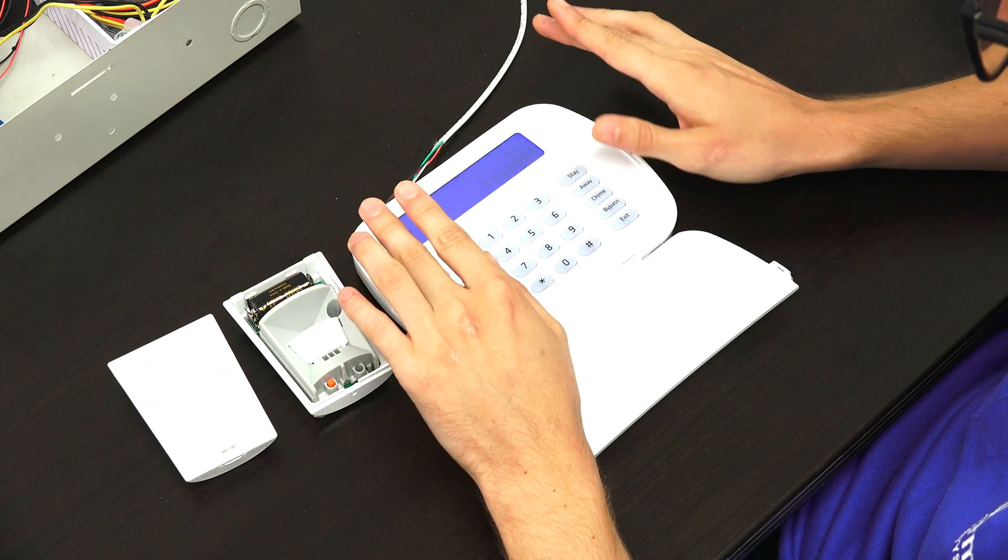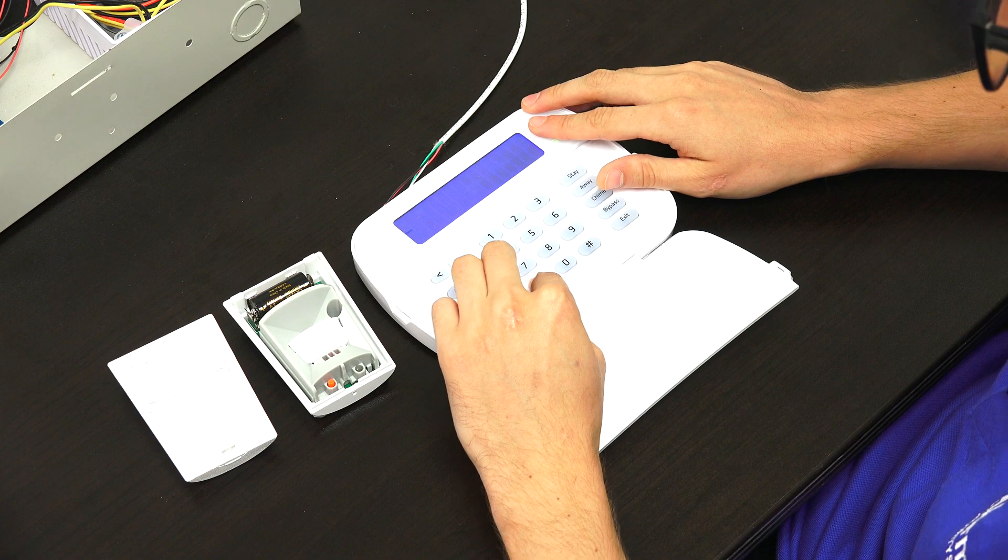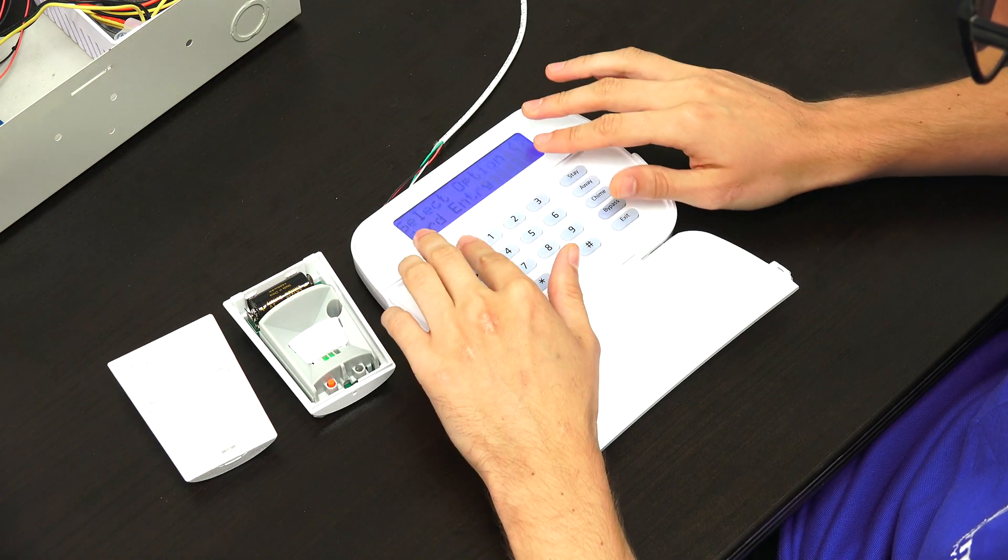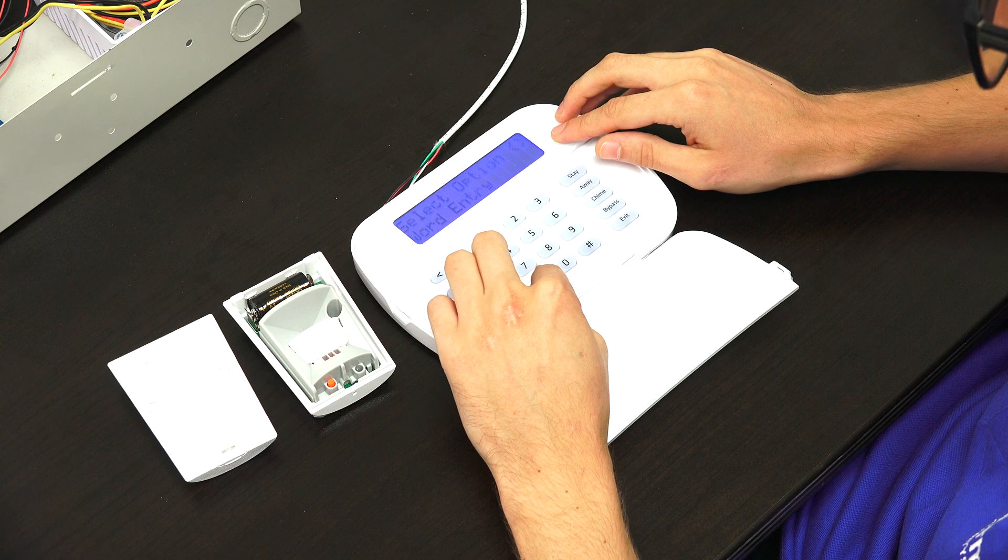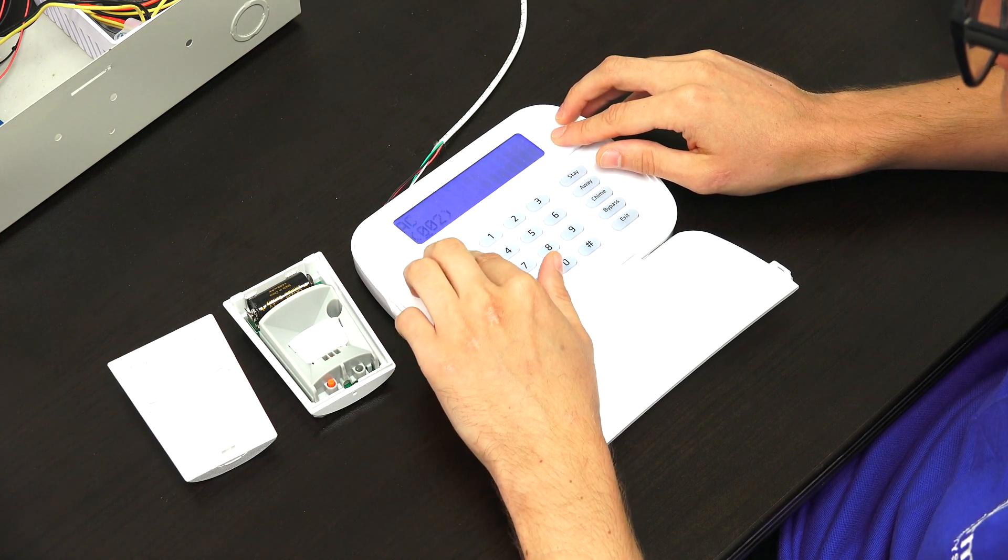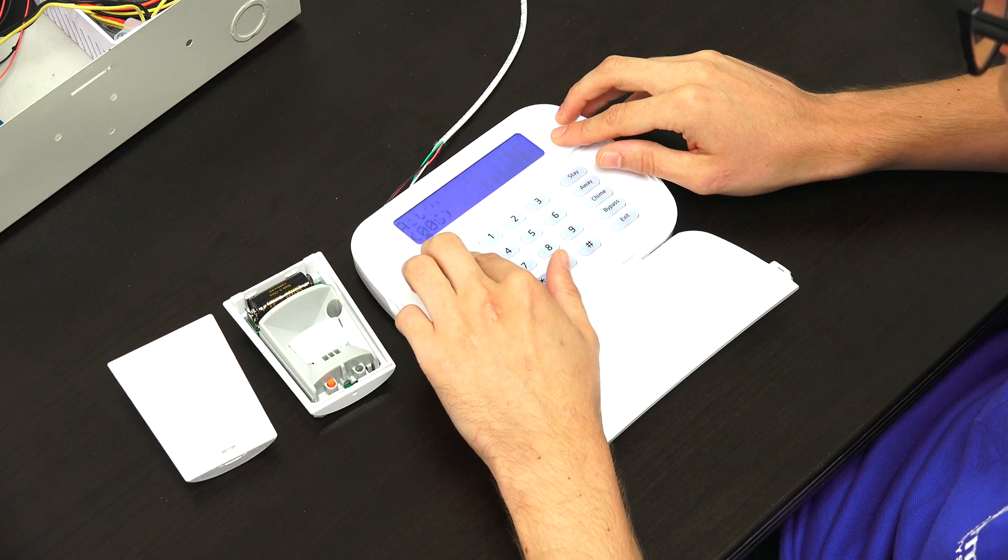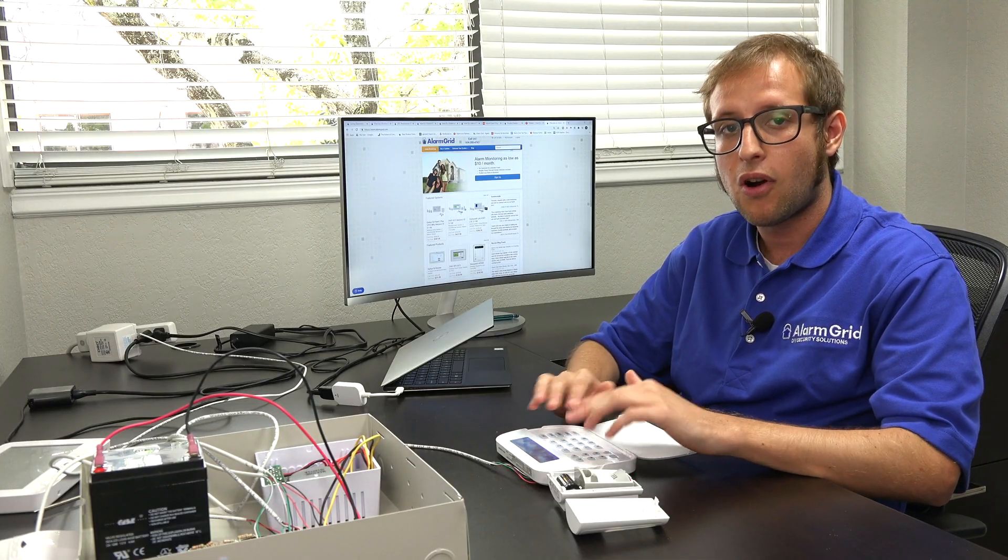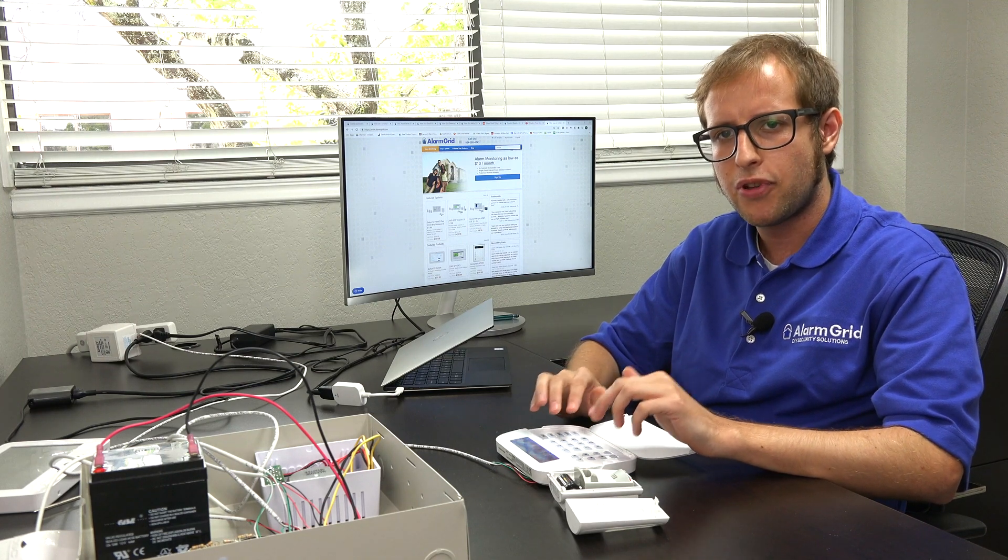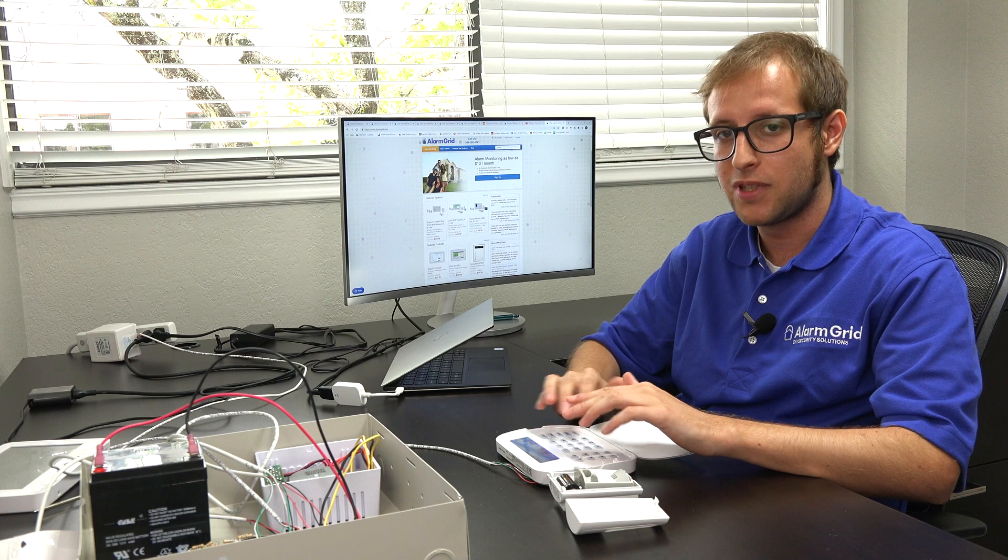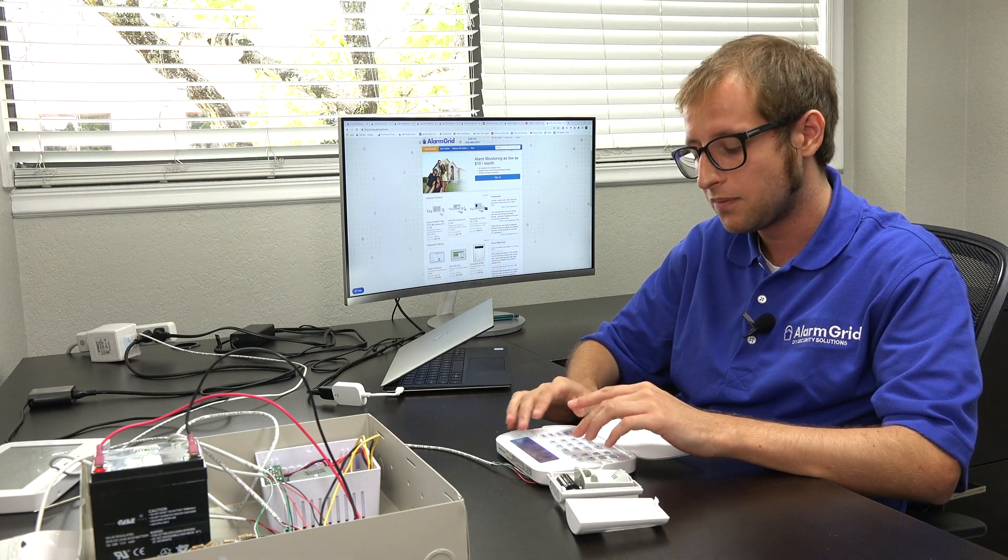So now we have our zone label completely cleared. And we're going to press star first to give us various options. And we're going to choose the word entry option. And we're going to press star again. And we can scroll between different words here. So the 001 through 193 are words.